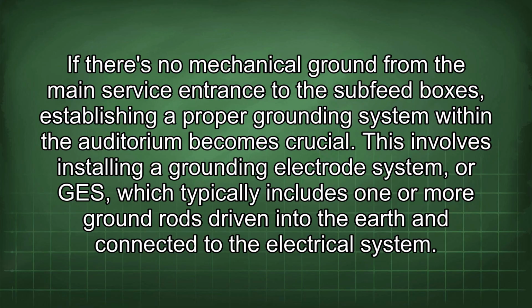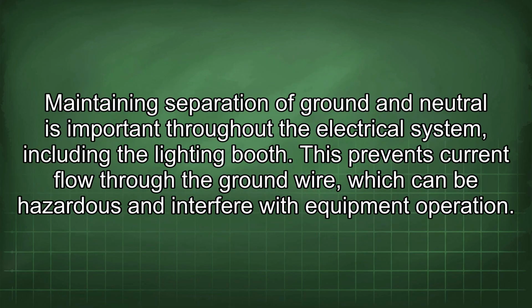This involves installing a grounding electrode system, or GES, which typically includes one or more ground rods driven into the earth and connected to the electrical system. Maintaining separation of ground and neutral is important throughout the electrical system, including the lighting booth. This prevents current flow through the ground wire, which can be hazardous and interfere with equipment operation.